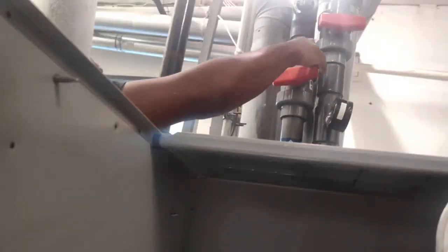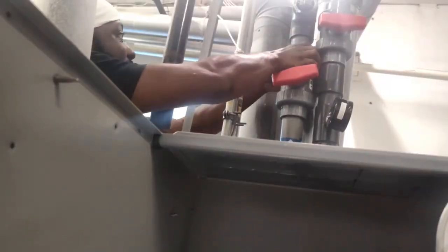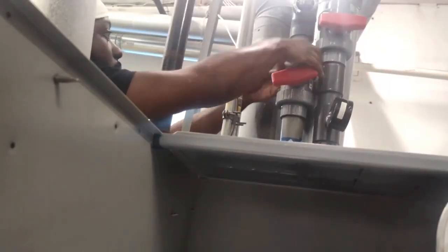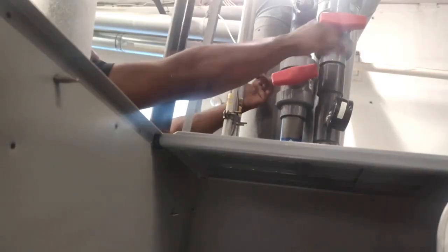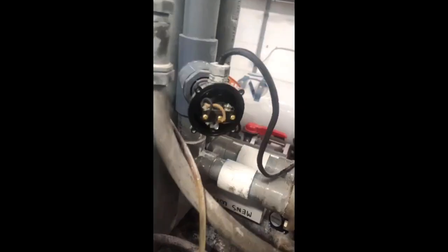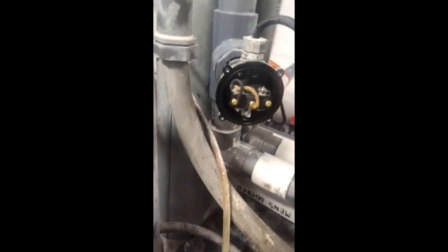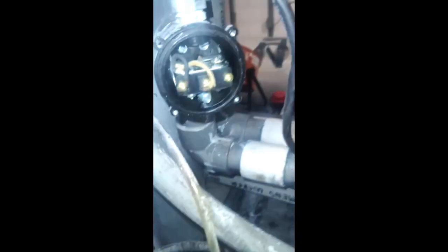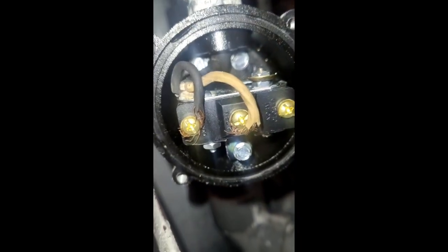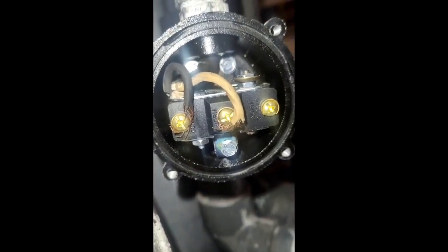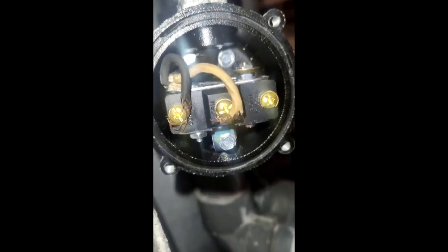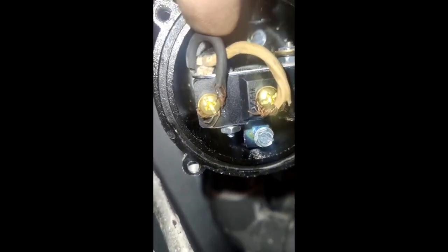So I closed off one side, valved off both sides. One of them actually didn't close all the way, which I just found out. But that's the old flow switch right there. It's got normally open with the white wire, and whoever put that on there is ridiculous. That should not have been put on there like that. Black wire looks better, but we're gonna put some little fittings on there to make that a tighter connection. Got it off right there.